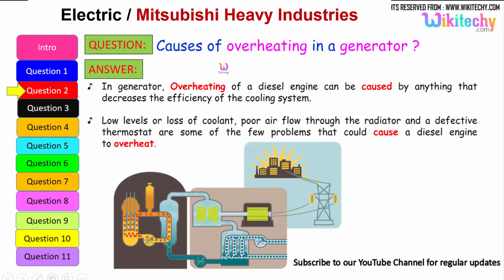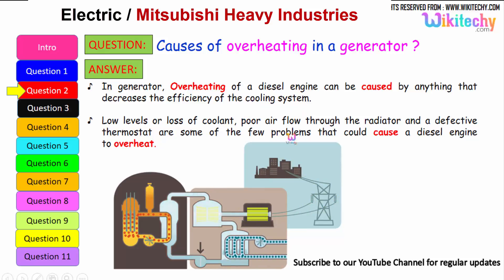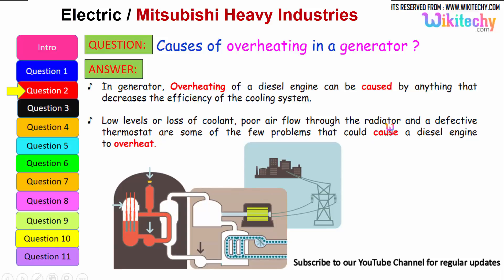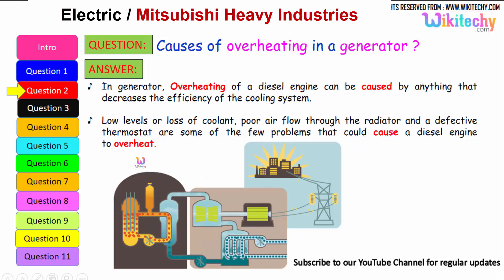Let us move on to the next question: causes of overheating in a generator. Overheating of a diesel engine can be caused by anything that decreases the efficiency of the cooling system. It can be due to loss of coolant or low levels of coolant, poor air flow through the radiators, and a defective thermostat — these are some of the problems that could cause a diesel engine or a generator to overheat.